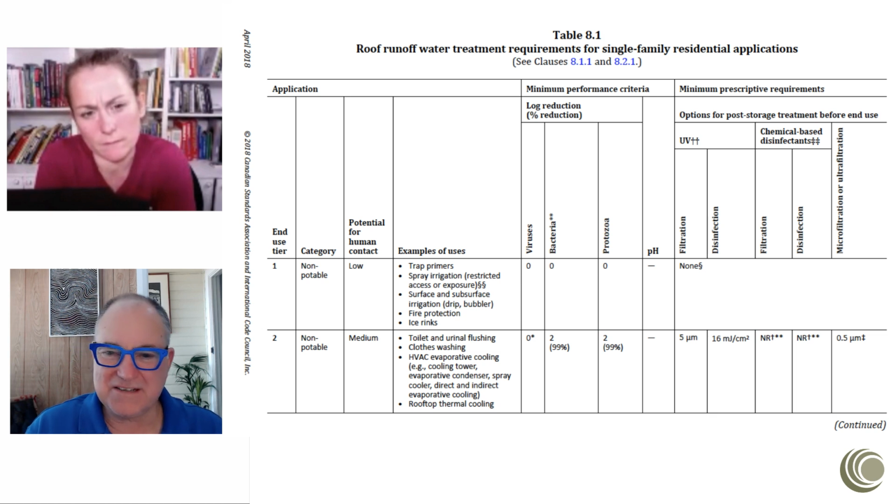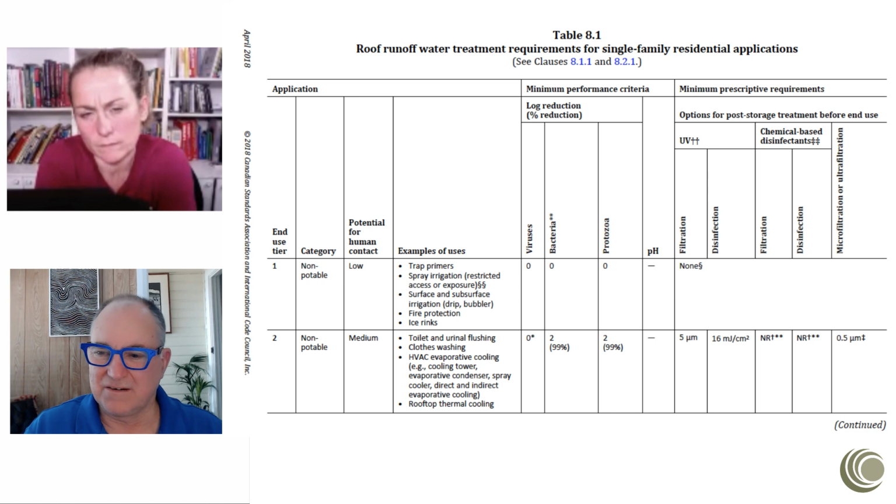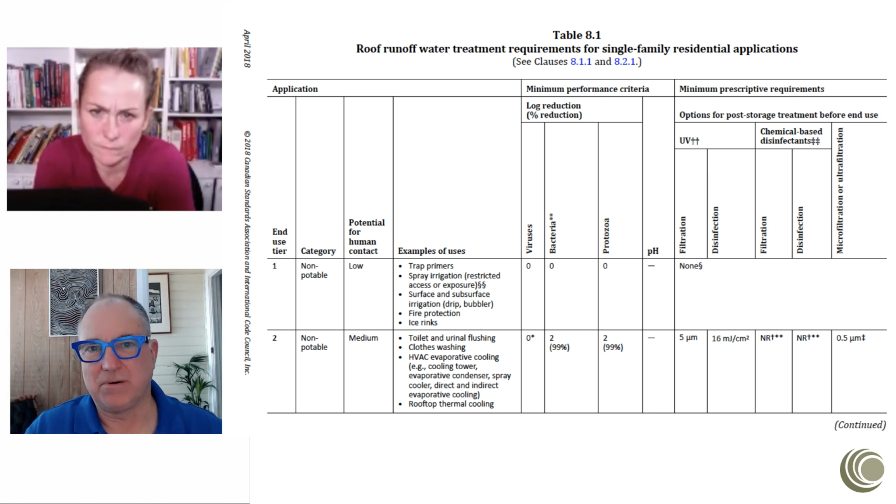Then there's this issue that you've quite rightly raised. The water quality depends on where you test in the rainwater harvesting system. We have lots of trouble in Australia where people just grab a sample through the top of the storage, and all they're sampling is the water surface micro layer, which we talk about in the treatment train part of this course, where anything that might be in the water stays at that layer, and that will not be at your point of supply.